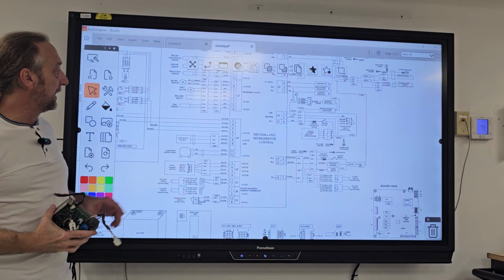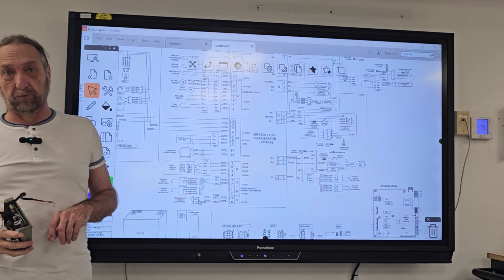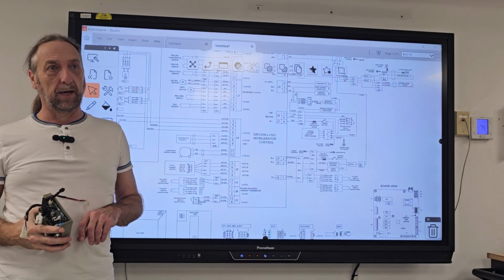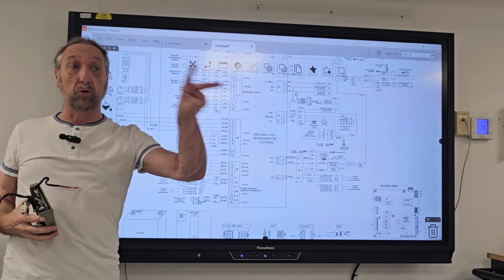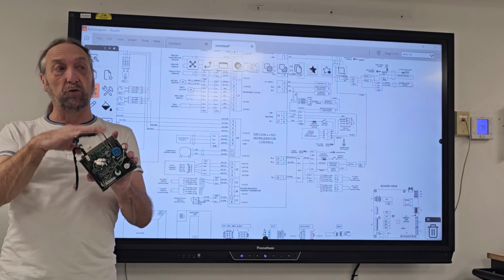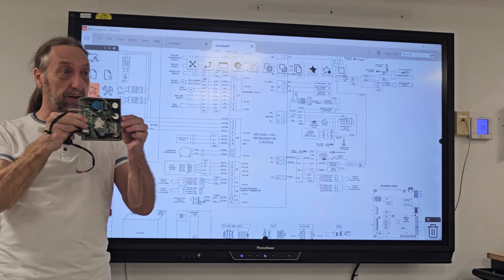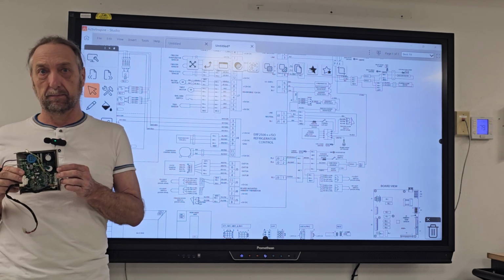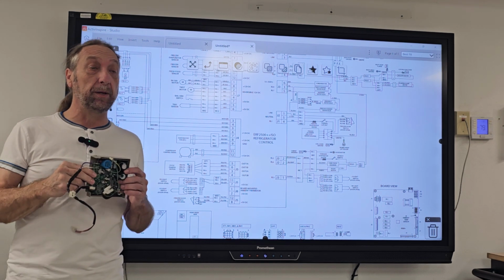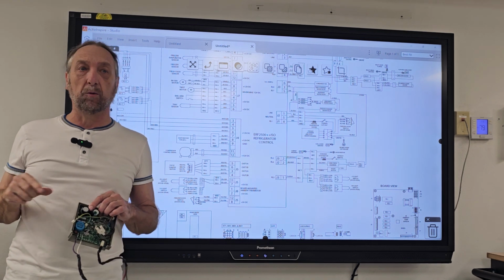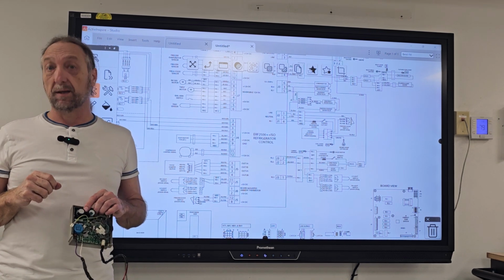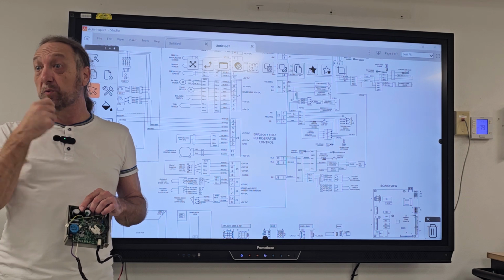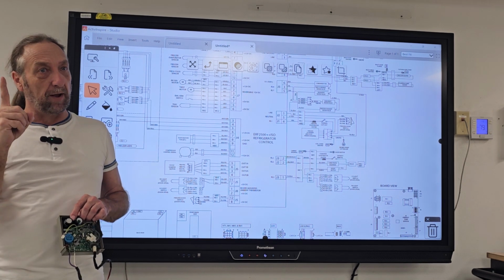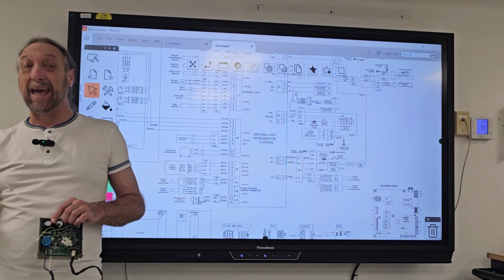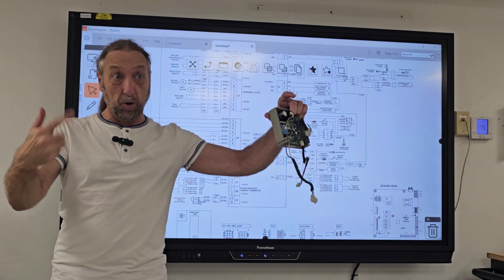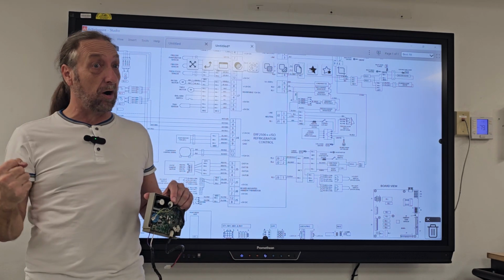But what about checking the actual compressor for ohms? Okay, if the windings ohm out good, and we have the two voltages and the compressor don't work, most likely the inverter board is bad. Can the compressor still be bad even though the resistance in the compressor checks good? Yes. Just because we have good resistance, the compressor is electromechanical. It has an electrical part, the motor, but it has a piston like a car, mechanical.